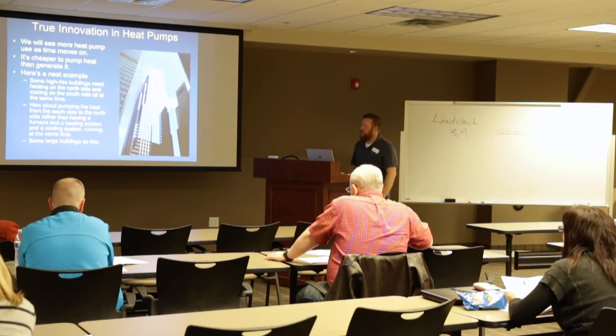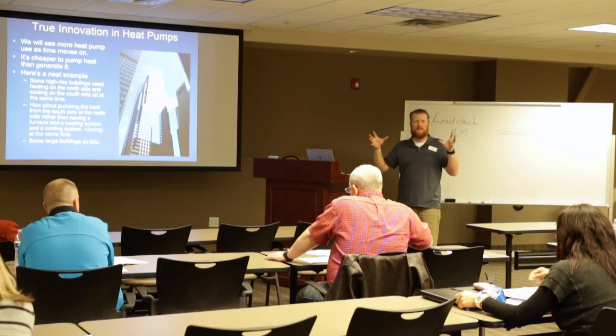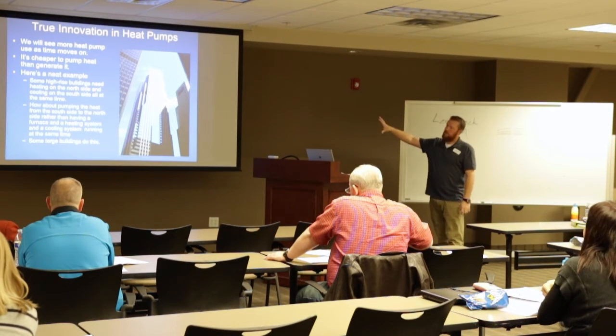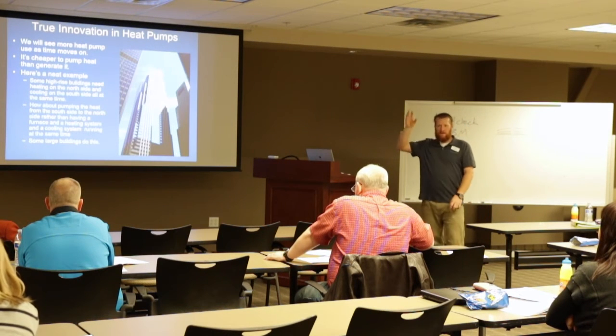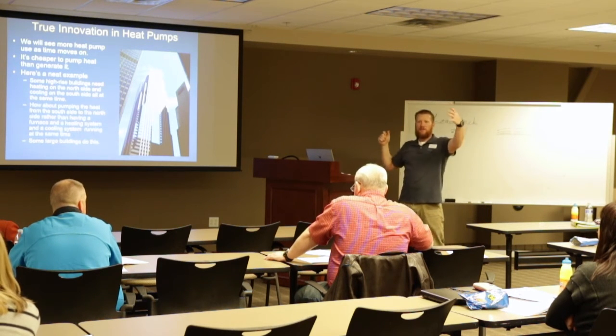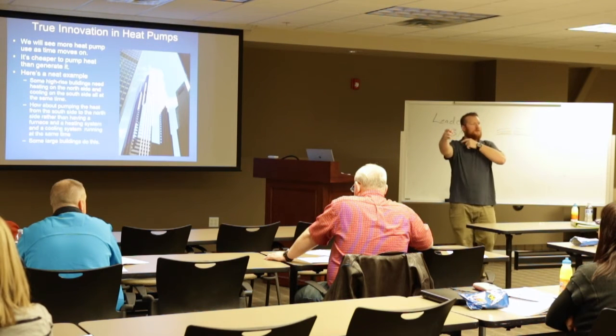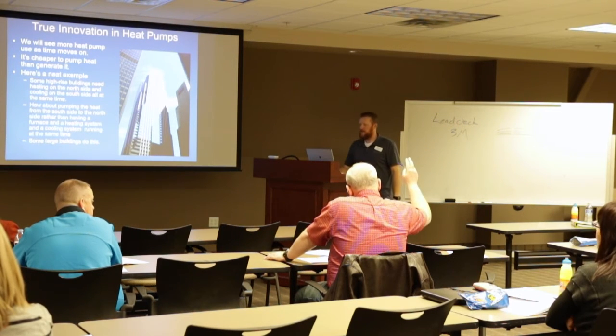Okay, like I said, we're going through this. There are some other cool things that they're trying to do with heat pump technology, because remember, the basics of a heat pump is that it's a device for moving heat from cold to hot. One application where they're starting to see it is big high-rise buildings, especially with tons of glass. On the south-facing side, by 11 o'clock in the morning they're cranking up the AC. On the north side, it's shaded, they might still be running the heater. So rather than all that consumption with air conditioning and heating, they're starting to install internal heat pumps that just move the heat from one end of the building to the other. And we've seen huge, dramatic cost savings and energy efficiencies.